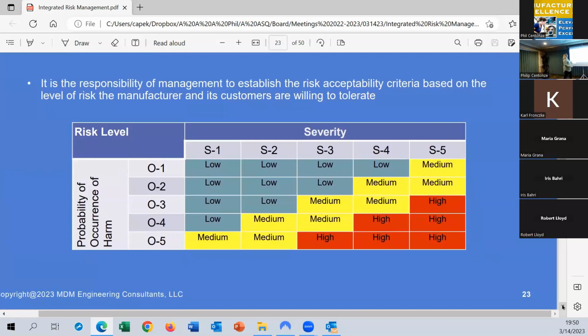So if I had a severity for harm and the harm could occur, let's say, occasionally, then my risk would be medium. Most manufacturers use a risk table like this. It doesn't really mean a heck of a lot, in a sense, because the FDA doesn't really want you to have a lookup table that says, oh, I'm low, I'm good, I don't have to reduce my risk. In the medical device world, you want to reduce risk as low as possible all the time, right? In fact, they took language out of the standard that used to say "as long as it's technically and economically feasible." They really want you to reduce risk as much as possible. Obviously, there are still technical and economic constraints.